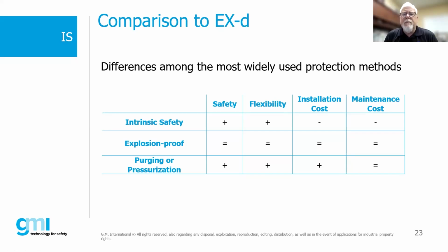Installation cost - we've done some studies and some webinars. Actually, we did a webinar here not too long ago on some of the cost differentials between the different methodologies, and I would hope you go check that out. But we looked at an installation basically going intrinsic safety for, say, transmitters versus going with the same exact transmitters, doing it either flame proof or explosion proof. And you can find that the cost of actually doing an installation can be significantly less.